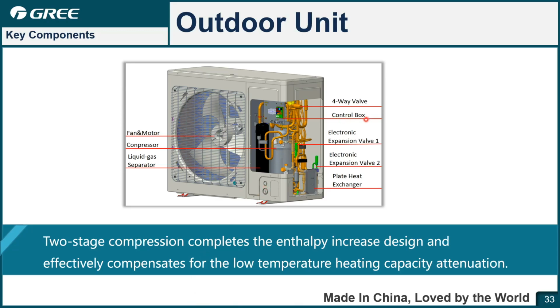And here is the control box. You can see some indicators and wiring terminals for the valve. And at the bottom of the chassis there is an e-heater. Actually, the VERSATI 3 has two-stage compression, which means the operation range is wider. Even in a very cold winter, the unit can still run very well.